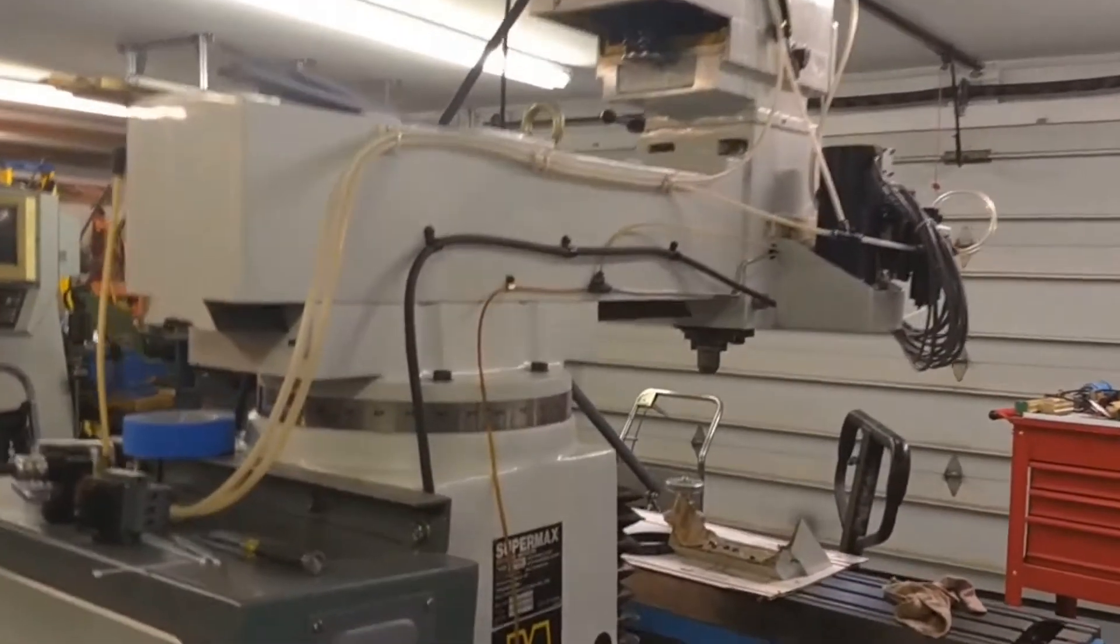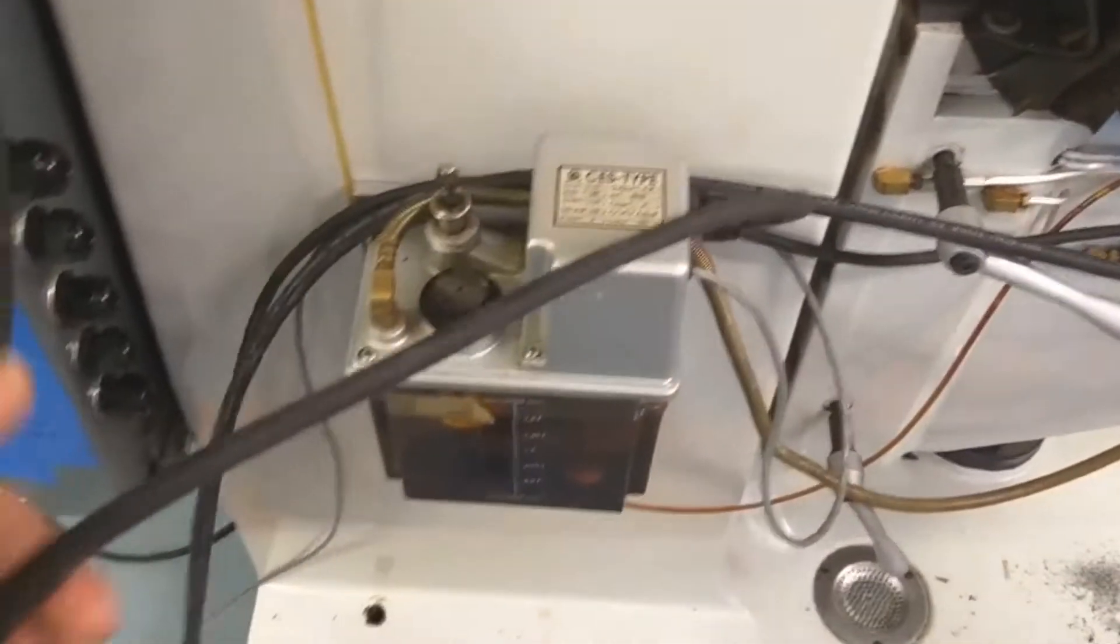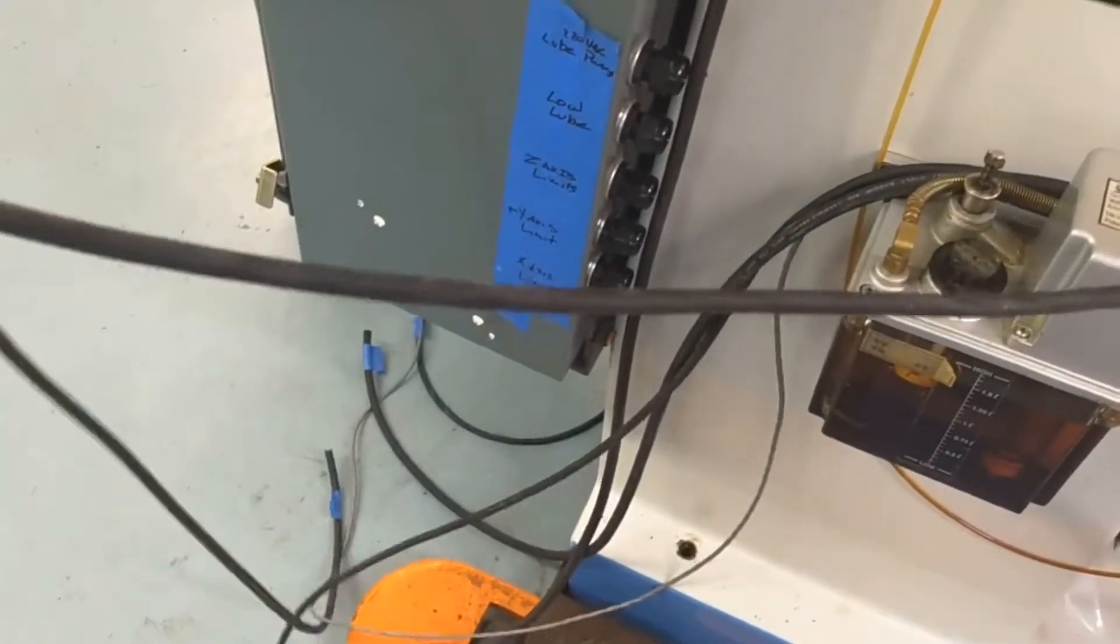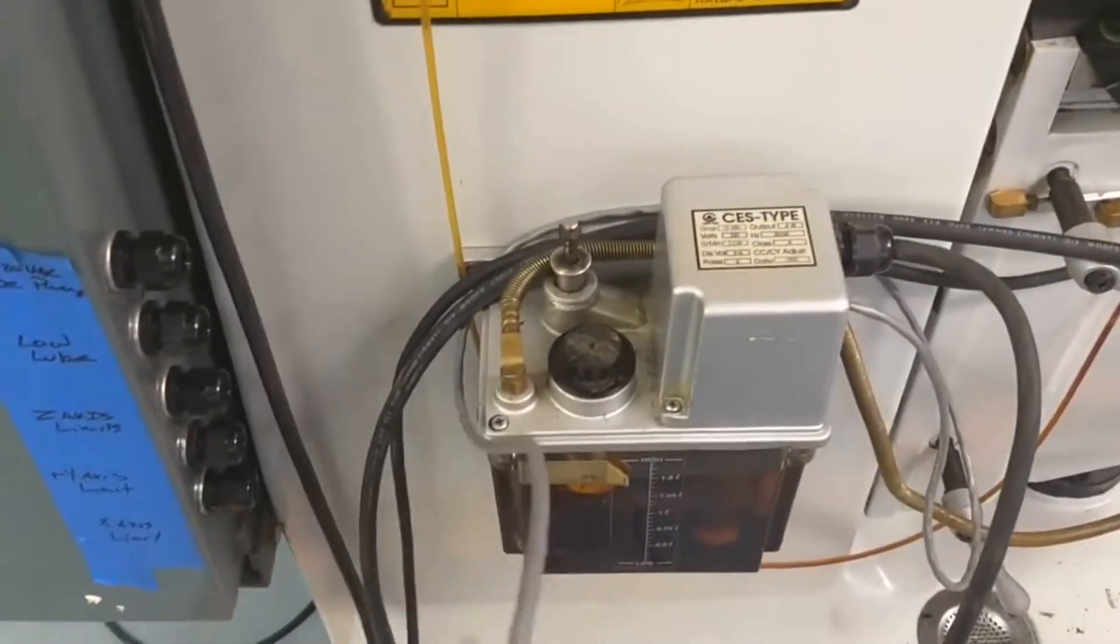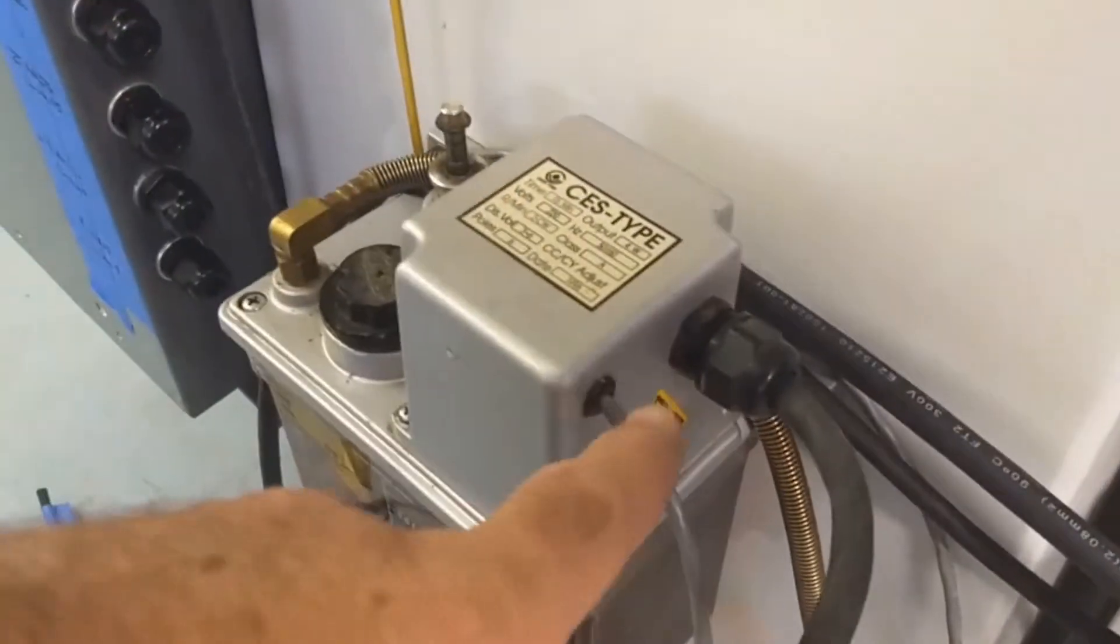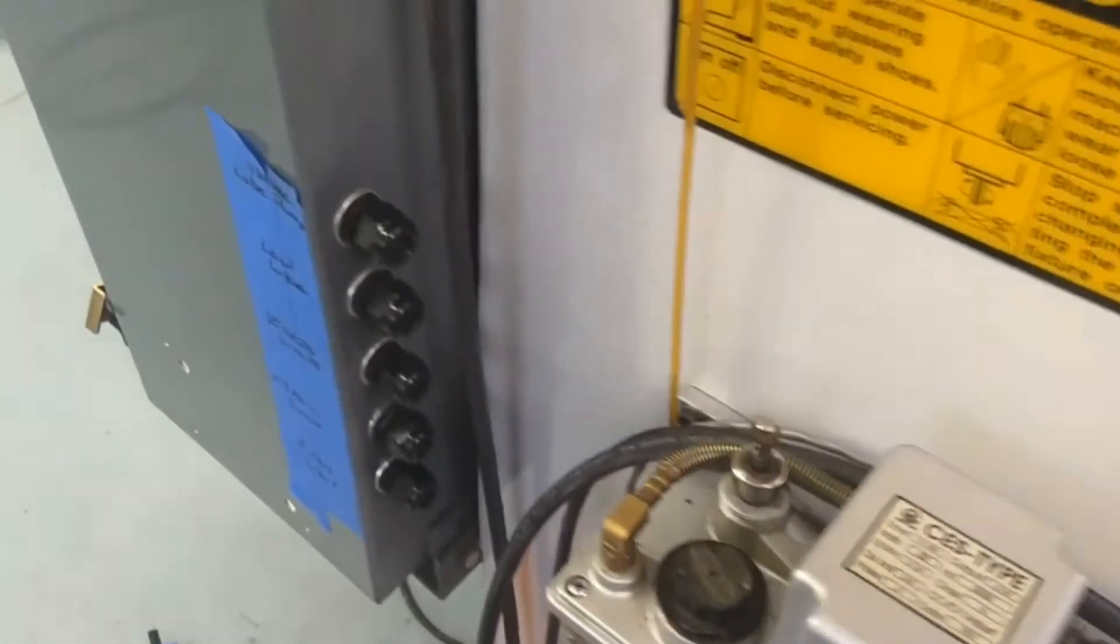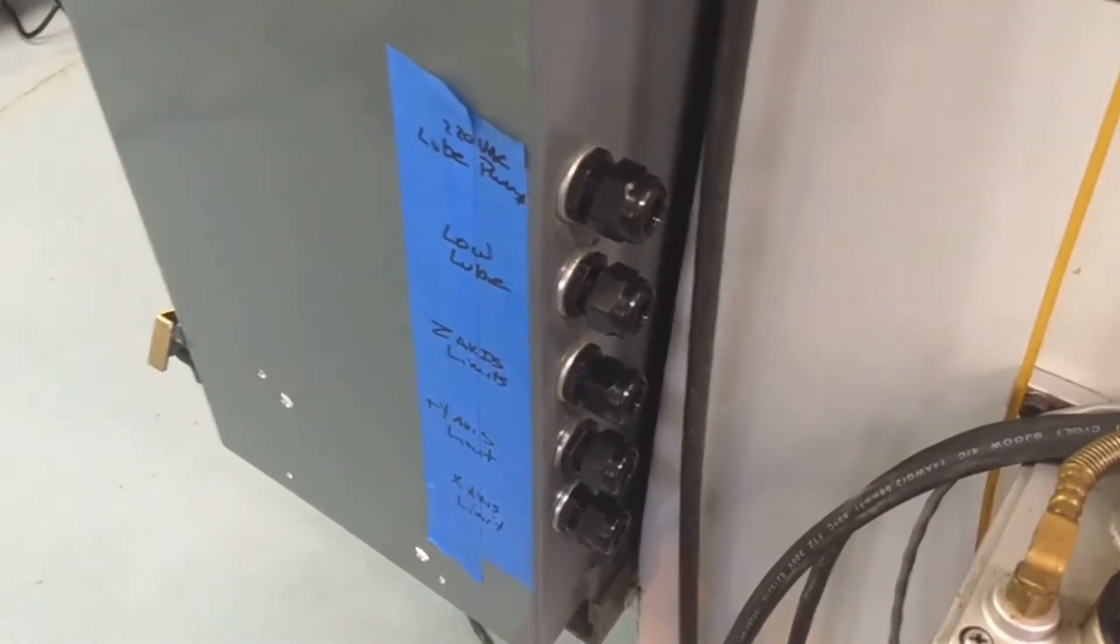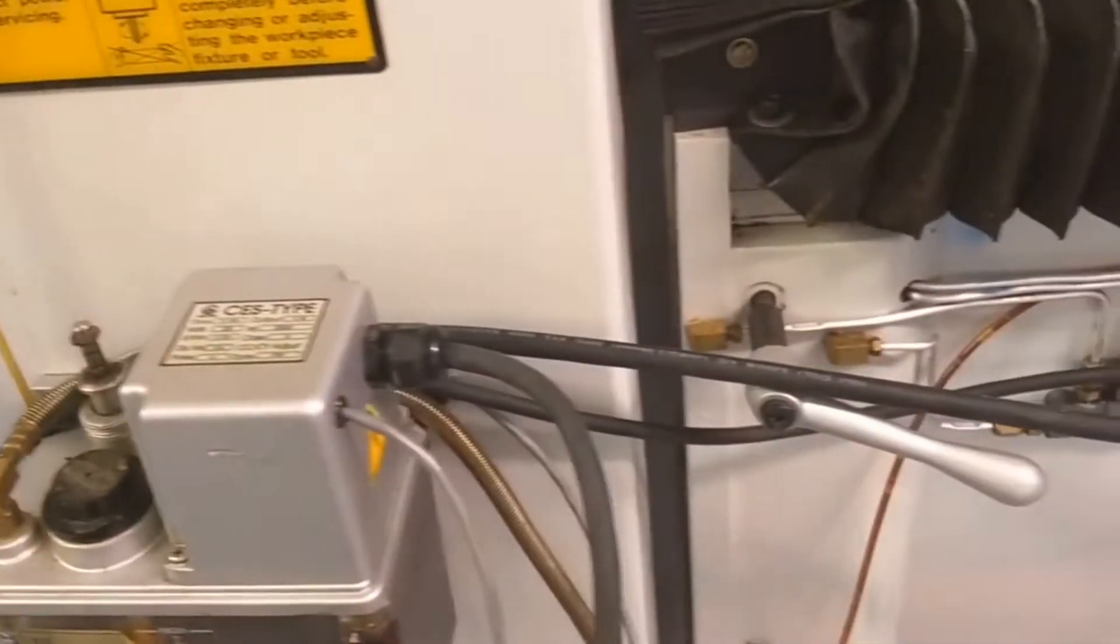Okay, I've got everything rewired. Let's start on this side. Here's the lube pump, got a new cord on it ready to go into the control cabinet. And then here this pump had a low lube alarm switch, so I drilled and put a bushing in there and wired up the cable to the low lube switch. I got strain reliefs in existing holes in the cabinet and I went ahead and labeled them so I know which cable goes into what connector.